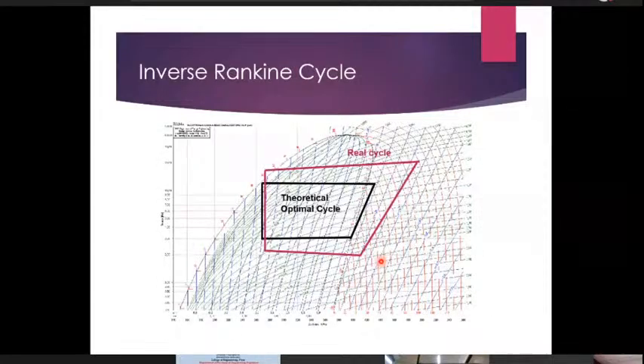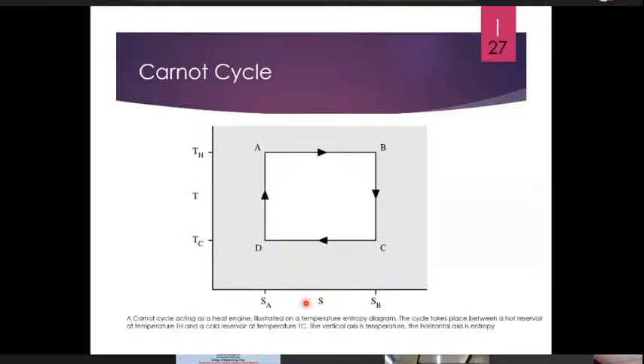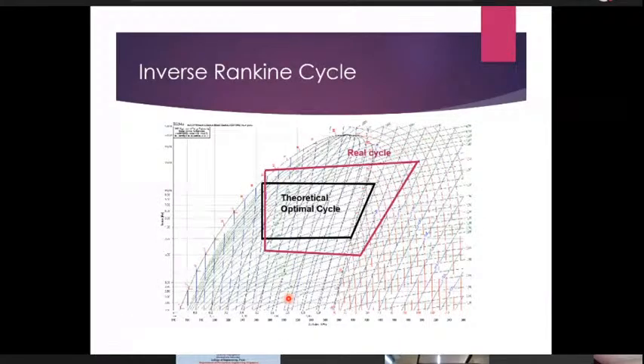Now, a real system, because we would not like to have compression in the two-phase region. So now we are moving from a temperature entropy diagram to a pressure enthalpy diagram. So this was temperature on the y-axis, entropy on the x-axis, and now we are switching to a pressure enthalpy diagram. So here we have pressure, we have enthalpy, and we have the saturation curve. All of the region inside this curve is a mixture of refrigerant liquid and vapor. And there are lines on this chart which will tell us the quality of vapor, like what percentage of liquid and what percentage of vapor.